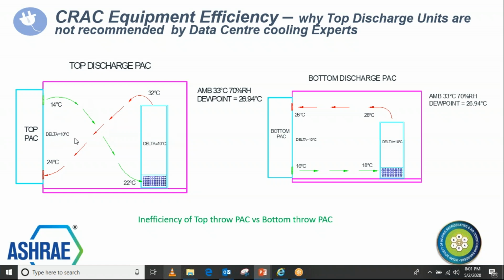So there is mixing happening here. This is very important because the cold air, having higher density, comes down, and the hot air is supposed to go up, but because a lot of suction, negative pressure, is created here, the hot air is coming down and going through here. So there is mixing happening, and you lose the effect of the hot air, you lose the hot air temperature. You are supplying cold air, but because of the mixing, the return air temperature to the cooling unit comes down. When the return air temperature comes down, the capacity of the cooling unit also comes down. At the same time, kilowatt per TR also increases, because the capacity has come down and it consumes almost the same power, with a little bit of difference. So kilowatt per ton goes up here.